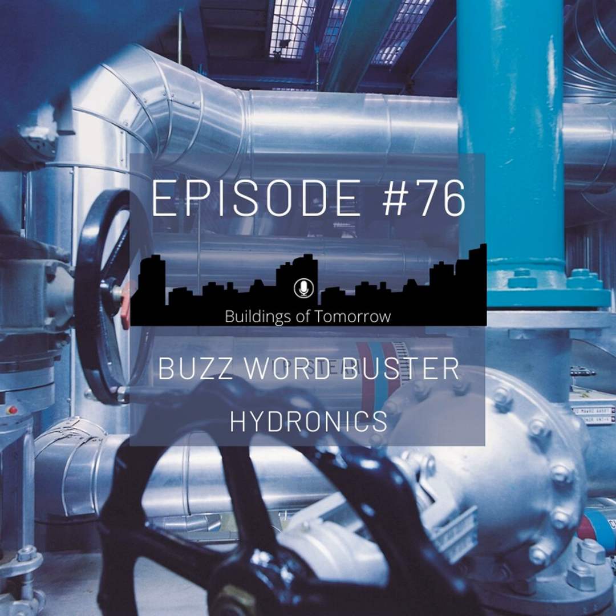Amazing. Now, one of the other parts that we see when we're sizing KVS valves, one of the important parts is to understand the valve authority or the P index V of that KVS valve. Can you give us a bit of an insight into the valve authority? Yes. So the valve authority, P index V, is an indicator of good controllability, you could say. And as a rule of thumb, we say it should be 0.5 or a little bit higher. And in other terms, it means that the resistance across the valve that we basically put into this hydronic circuit by selecting the appropriate valve size has to relate to the part that the valve wants to control, and this part we call delta P MV, and that's another term, but it nicely fits now.